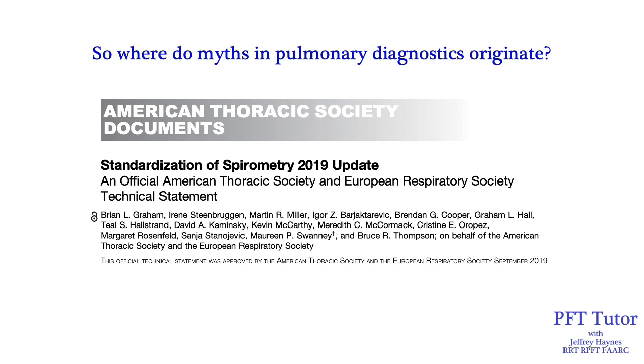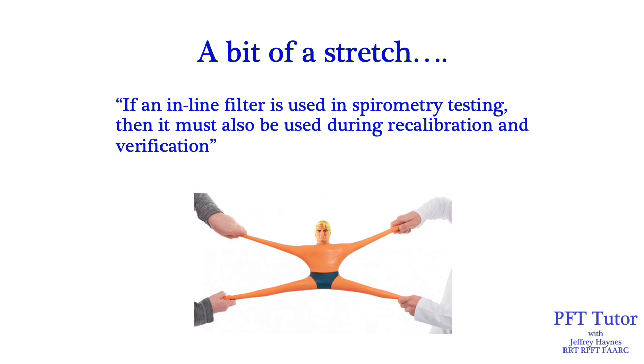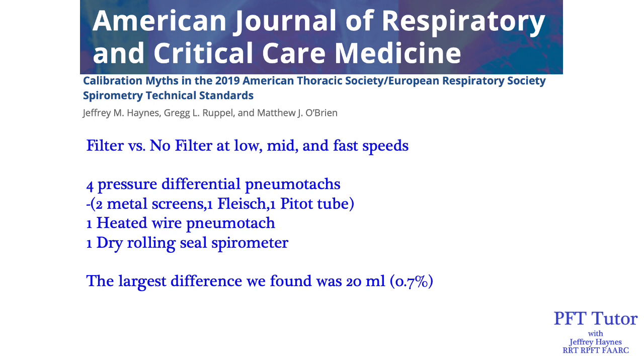Where do myths in pulmonary diagnostics originate? Sometimes these myths come from the ATS-ERS technical statements themselves. For example, in the 2019 spirometry standard, there is the statement that if an inline filter is used in spirometry testing, it must also be used during calibration and verification. We studied this idea and had it published in the American Journal of Respiratory and Critical Care Medicine. We compared filter versus no filter at low, medium, and fast speeds using four pressure differential pneumotachs — two metal screens, one Fleisch pneumotach, one with a pitot tube — plus one heated wire pneumotach and one dry rolling seal spirometer. The largest difference between calibrating with and without a filter was 20 ml, or 0.7%. Most of the time, we saw no difference at all.